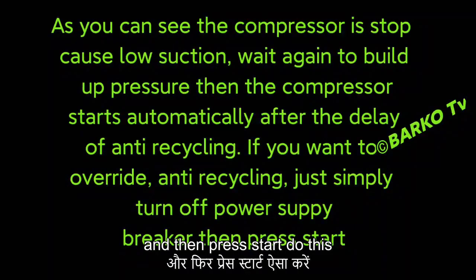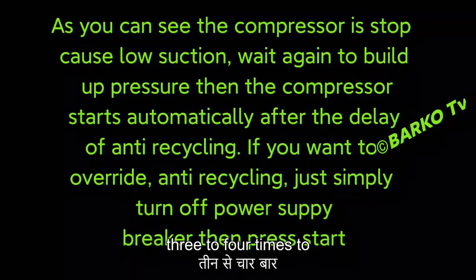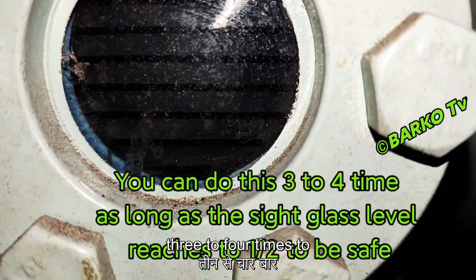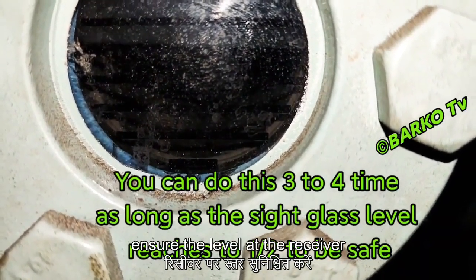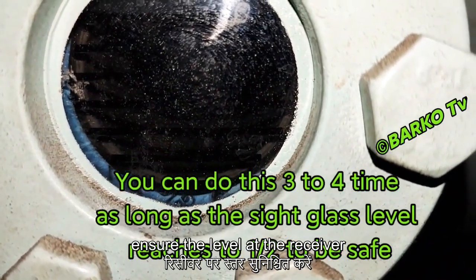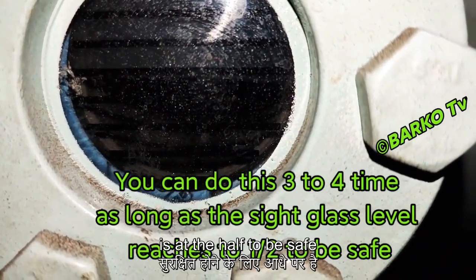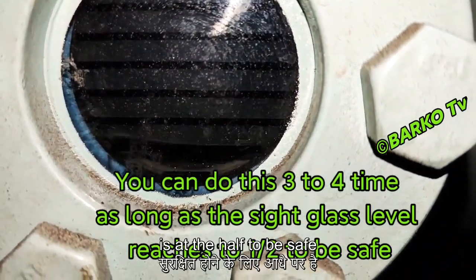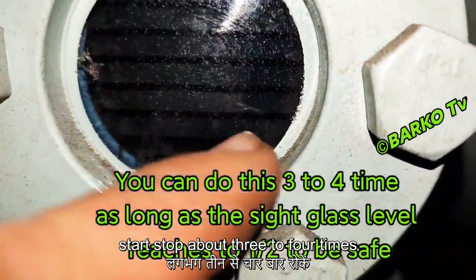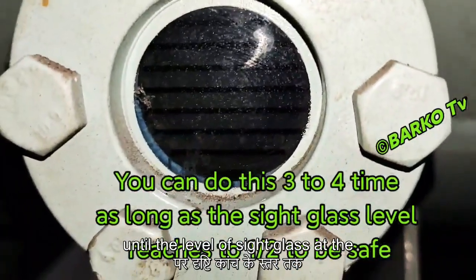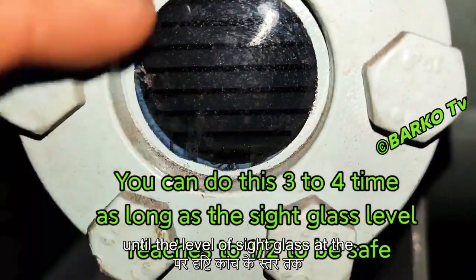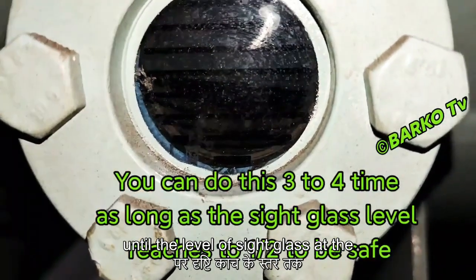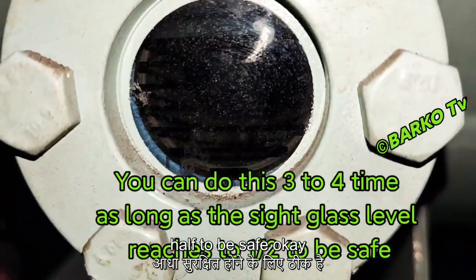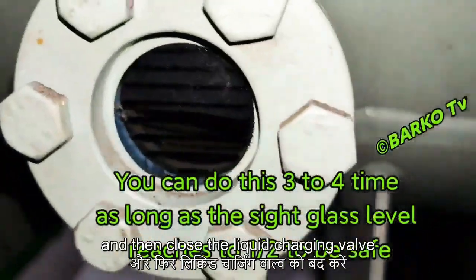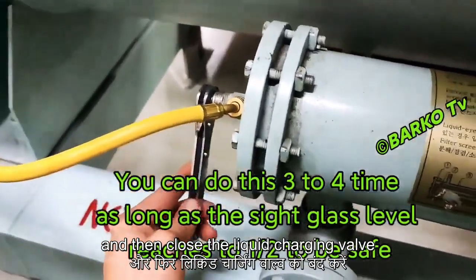Do this 3 to 4 times to ensure the level at the receiver is at the half to be safe. Stop about 3 to 4 times until the level of sight glass at the half to be safe. Okay, and then close the liquid charging valve.